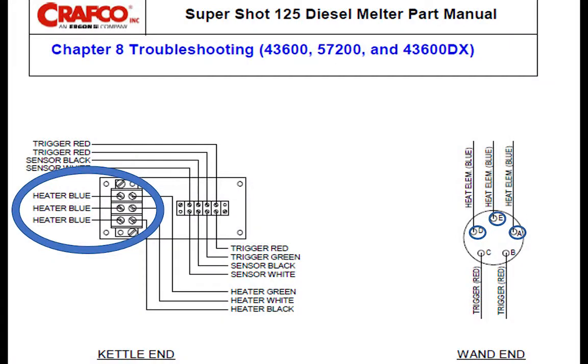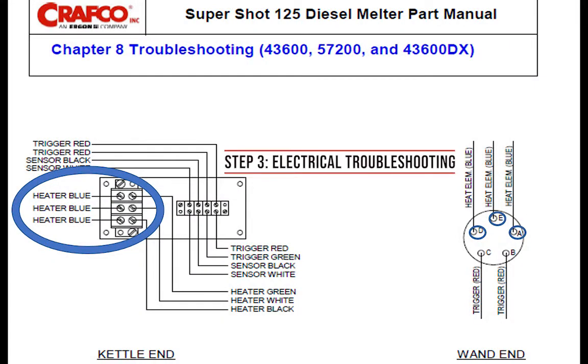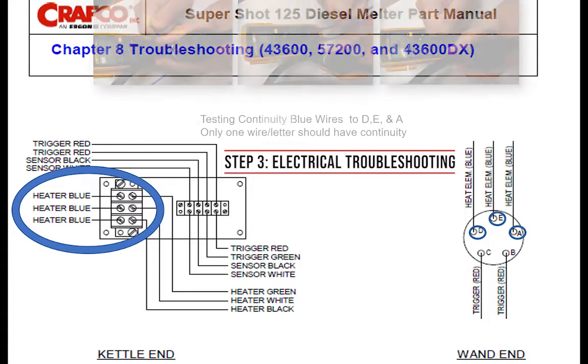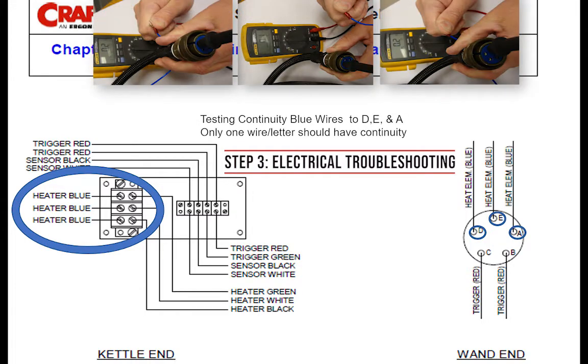Step 3 of electrical troubleshooting, we're going to check for continuity in the hose from end to end. To do this, you need to disconnect the 3 blue heating element wires from the terminal block inside of the junction box and disconnect the 5-pin plug between the hose and the wand. We're going to check each letter D, E, and A on the 5-pin plug against the 3 blue wires on the other end of the hose.